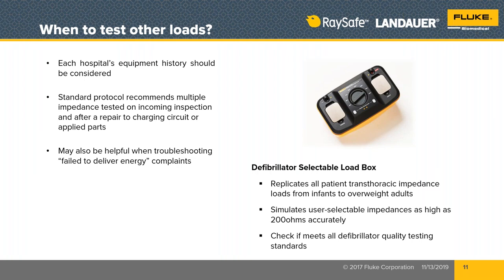So we say there's typically three different situations where you need to be able to do this testing. Some manufacturers require that you do this testing as part of their service manual procedure, but you should do this testing as part of your acceptance or incoming inspection test for any new defibrillator that's coming into your building before it goes into clinical use. Trust but verify. You need to see for yourself that this functionality is working properly. It may have been tested at the factory by the manufacturer you bought it from, but you need to see it for yourself. Objective, independent evidence that this functionality is working.